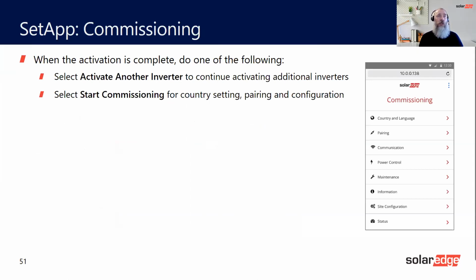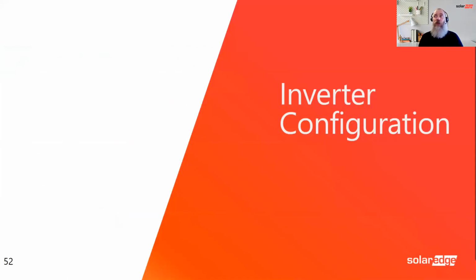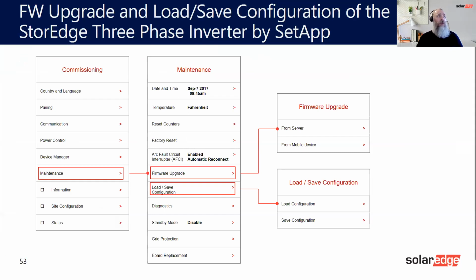So you've got the communication, the maintenance for arc fault circuit interruption, power control, and site configuration and status. So this is what we're going to look at now. This is purely for this product. So we go into maintenance, we go into firmware upgrade, and we upgrade from the server. Then we save the configuration and load it onto the battery. So all this is in the manual, so please don't worry. Once you've done a couple of them, it will become second nature.